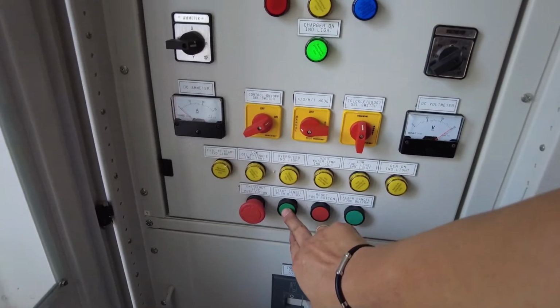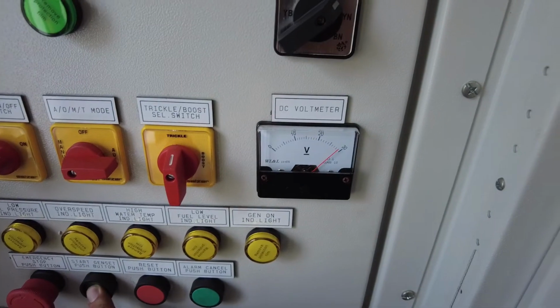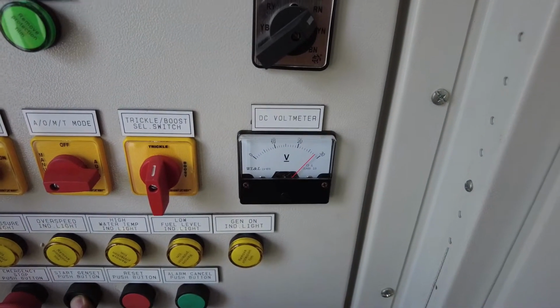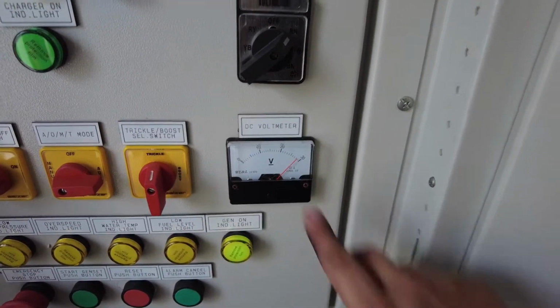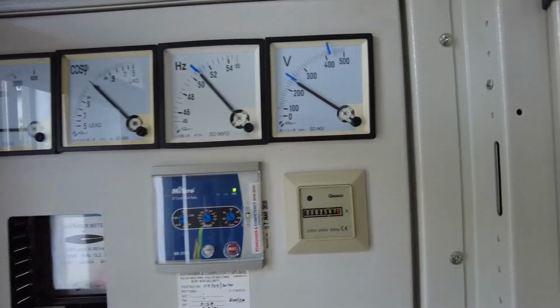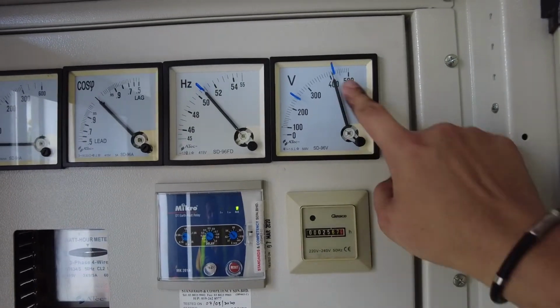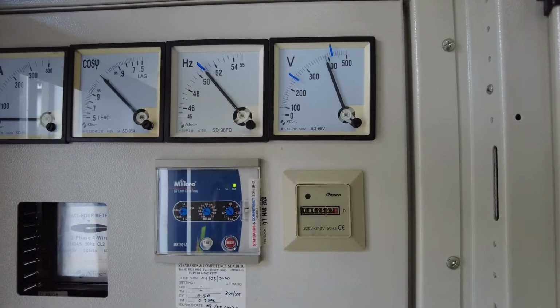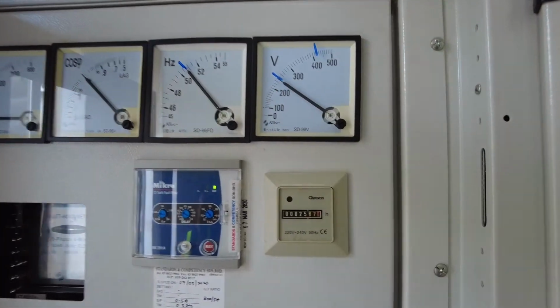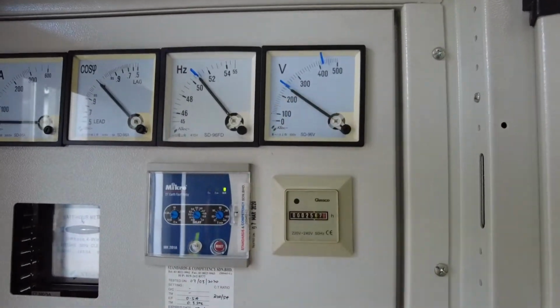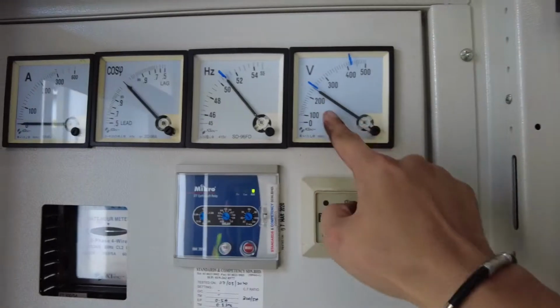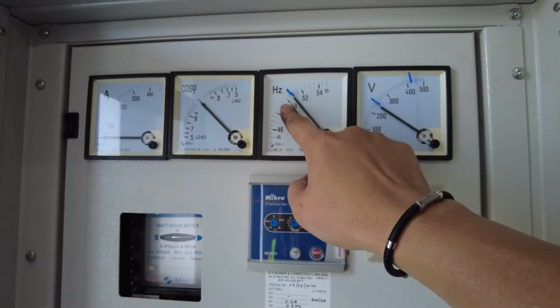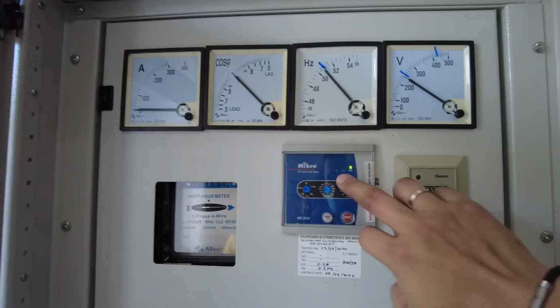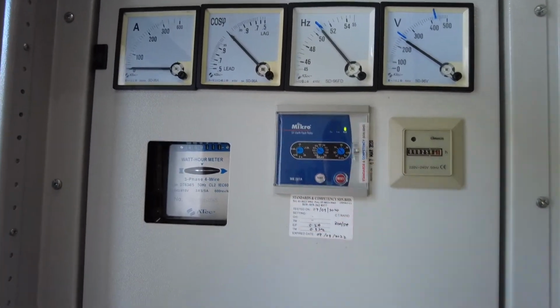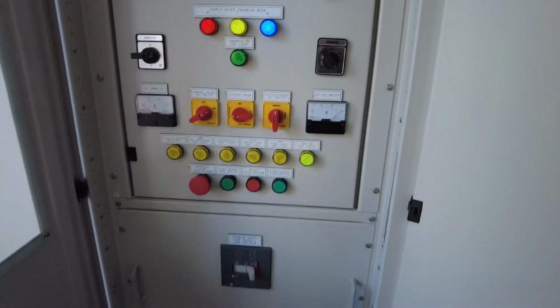Okay, you're going to start it. Okay, it's starting already. Okay, now the Genset is running. Let's check the voltage. 415. Okay, meet the mark. 230. Okay. Same frequency, same as previous, no problem. Protection relay function. Okay, all in good condition.